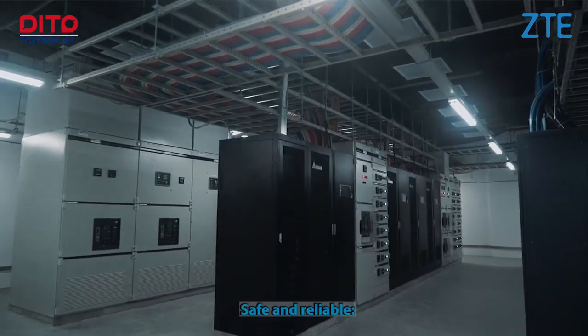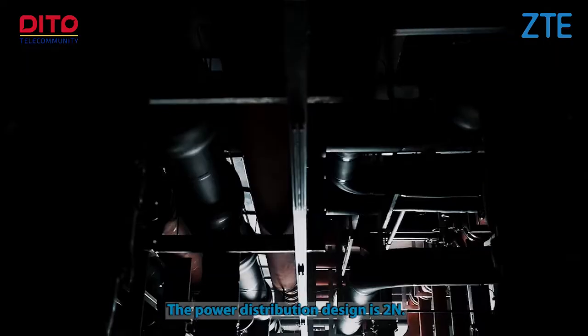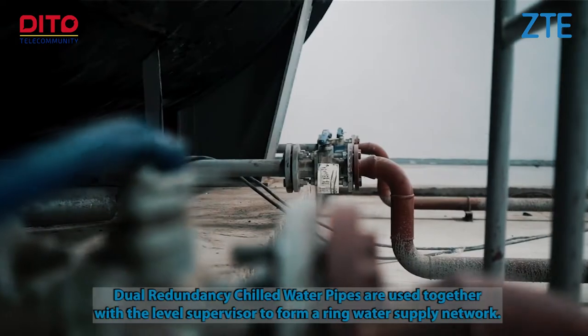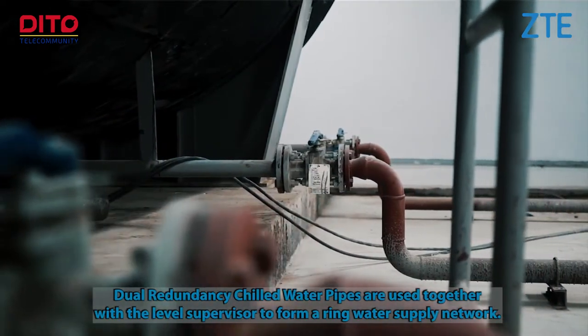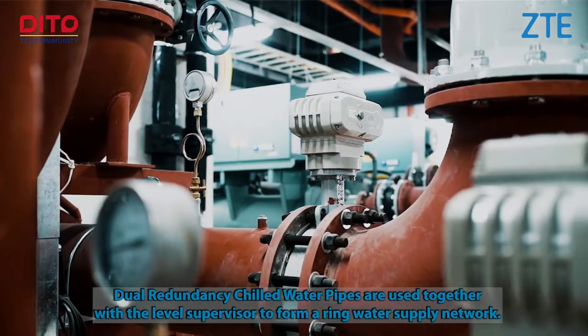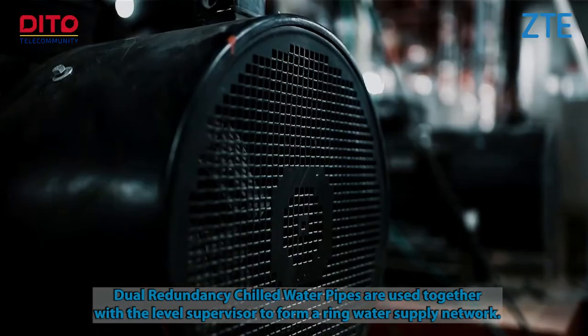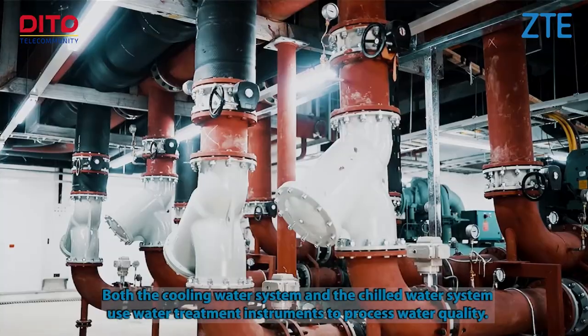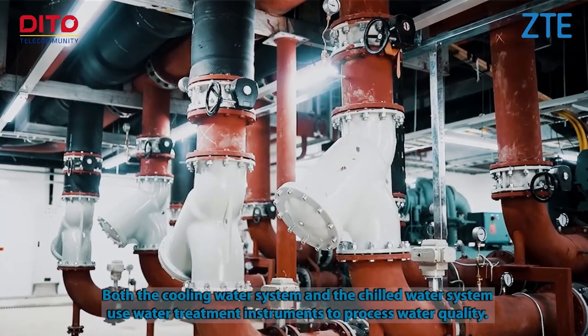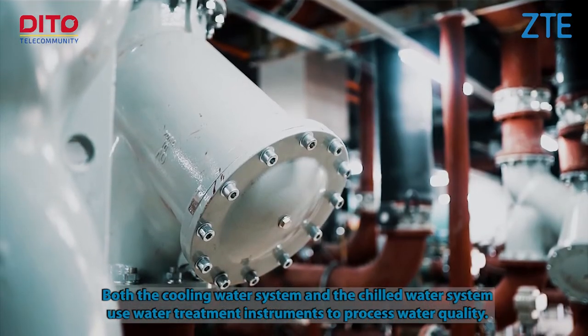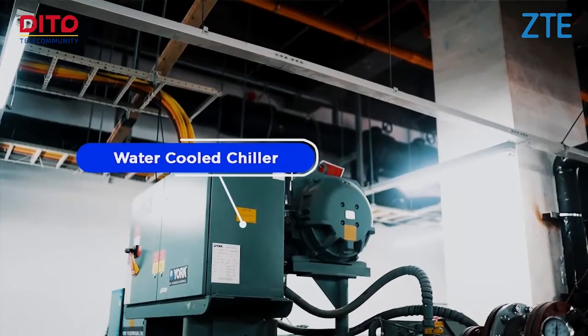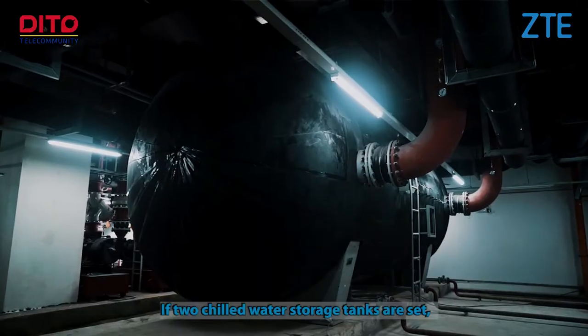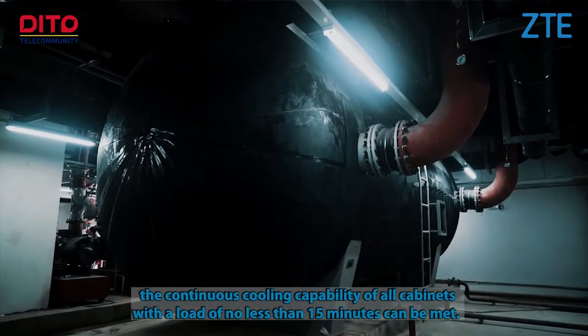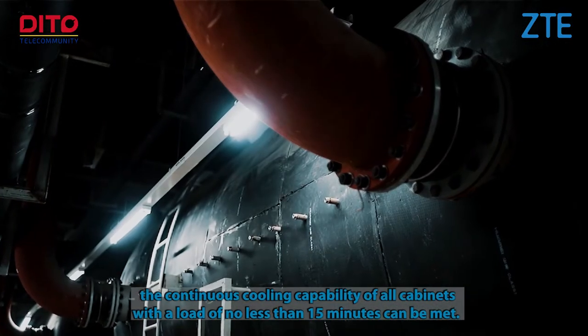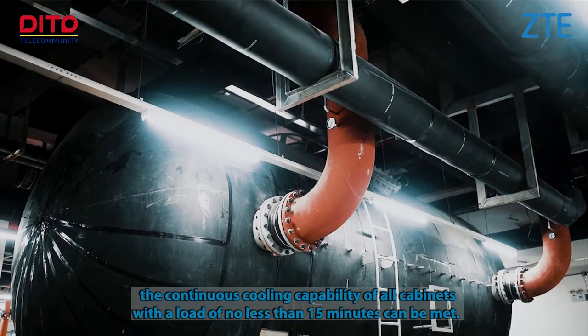Safe and reliable. The power distribution design is 2N. Dual redundancy chilled water pipes are used together with a level supervisor to form a ring water supply network. Both the cooling water system and the chilled water system use water treatment instruments to process water quality. 2 chilled water storage tanks are set, so the continuous cooling capability of all cabinets with a load of no less than 15 minutes can be met.